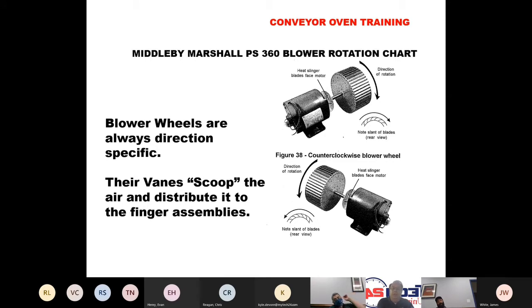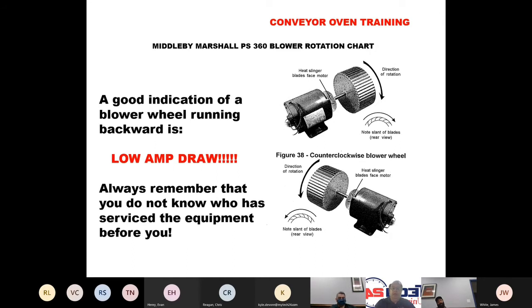The wheels of the blowers are always direction specific. They have vanes that are kind of like a cup, and they scoop the air and distribute it to the finger assemblies. A good indication of a blower wheel that's running backwards is low amp draw. Always remember that you do not know who serviced this equipment before you. Years ago, I went on a call that I had to drive about 2.5 hours to. Another company had changed the blower motor and it was running backwards. So it was a very easy call, but it does happen.